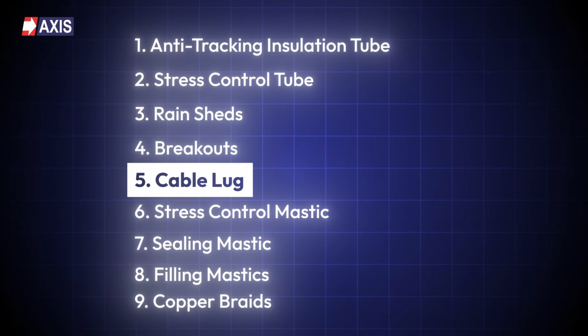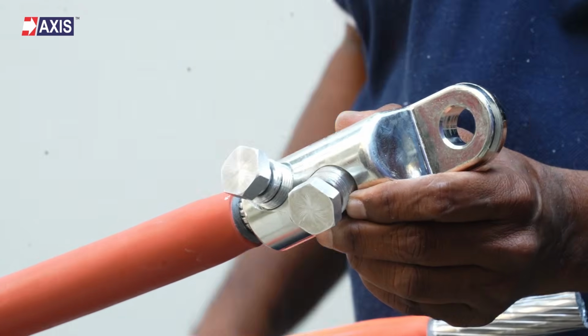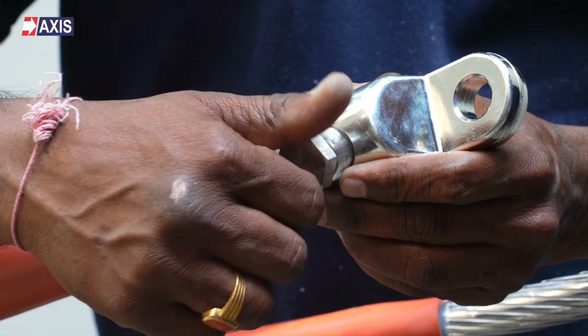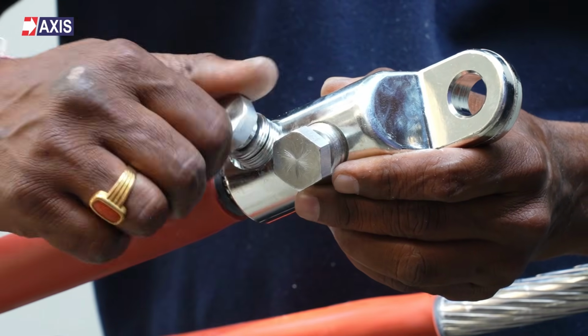Fifthly, the cable lug. This provides the mechanical and electrical connection between the cable conductor and the equipment terminal. It ensures efficient current transfer while maintaining a secure, low-resistance joint. Proper selection and crimping of the lug are critical, as poor connections will lead to overheating, voltage drop, and eventual termination failure.